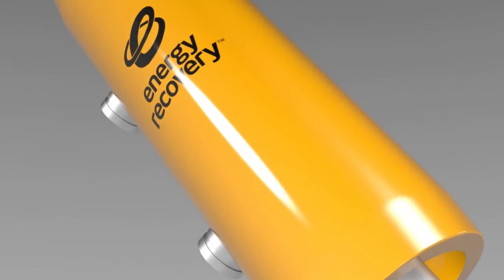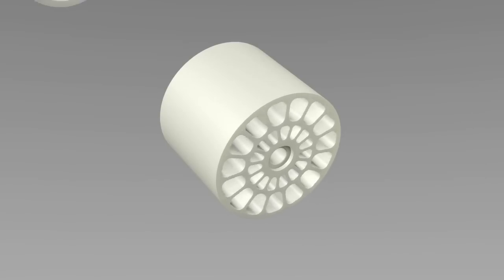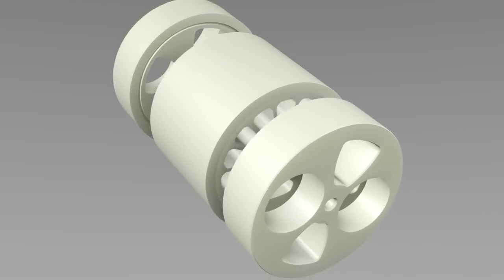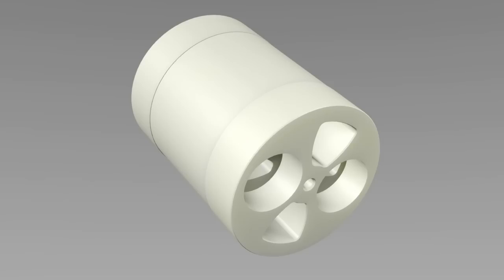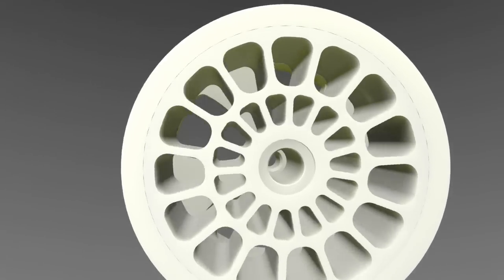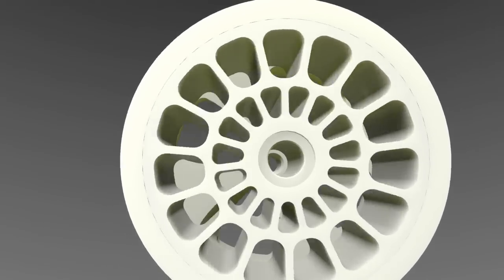Simply yet elegantly designed, the PX High Pressure Housing contains a ceramic rotor — the only moving part in the entire device. Surrounding the rotor are a sleeve and two end covers. These ceramic components fit snugly around the rotor to form a tight, fluid seal. Water in the narrow gap around the rotor acts as a hydrodynamic bearing, requiring no external lubrication.